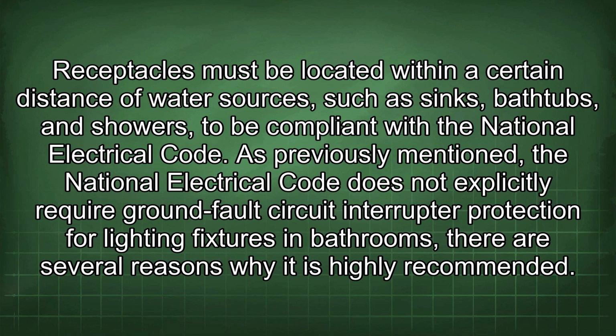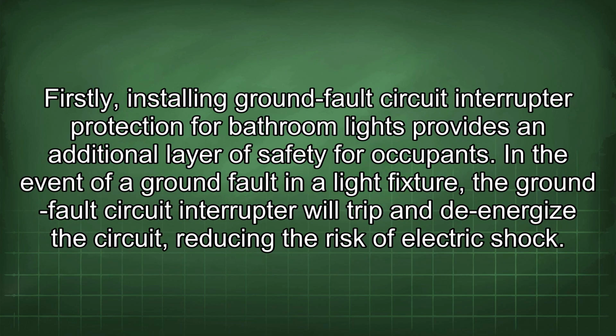As previously mentioned, the National Electrical Code does not explicitly require ground fault circuit interrupter protection for lighting fixtures in bathrooms. There are several reasons why it is highly recommended. Firstly, installing ground fault circuit interrupter protection for bathroom lights provides an additional layer of safety for occupants. In the event of a ground fault in a light fixture, the ground fault circuit interrupter will trip and de-energize the circuit, reducing the risk of electric shock.